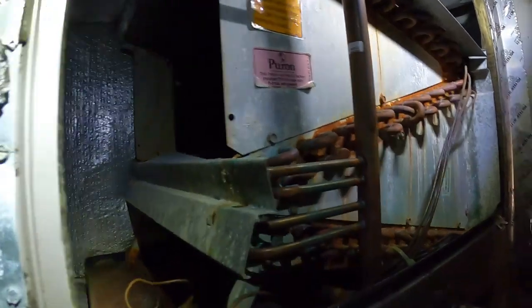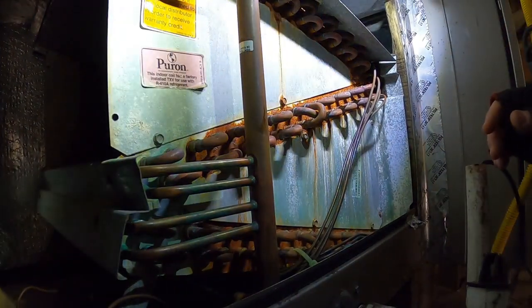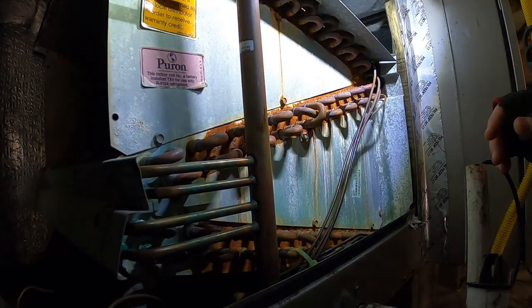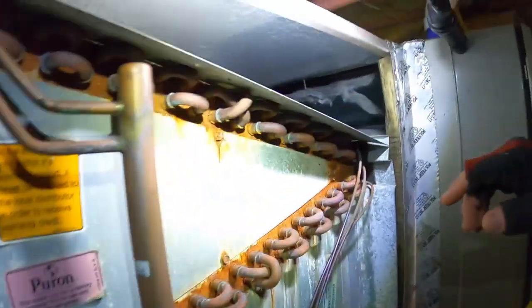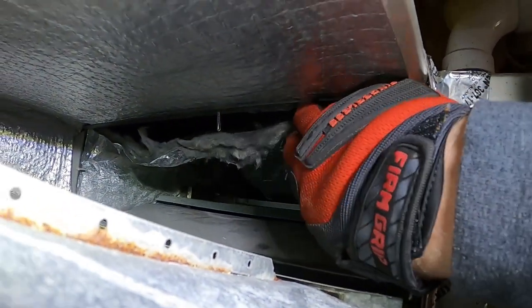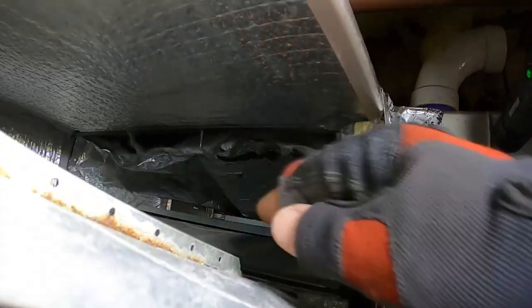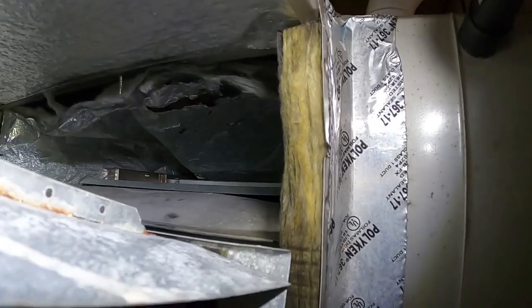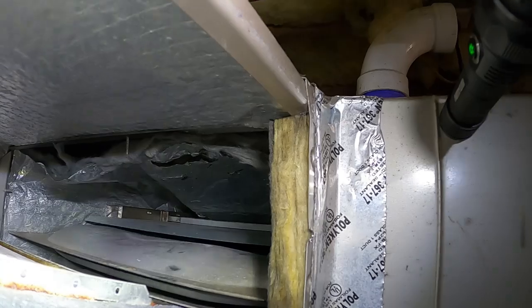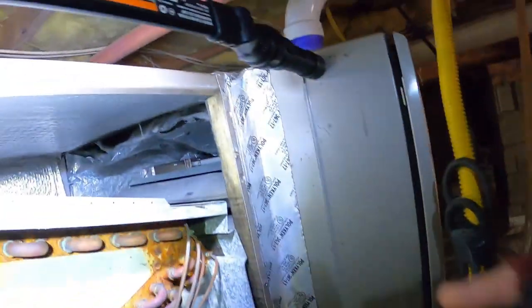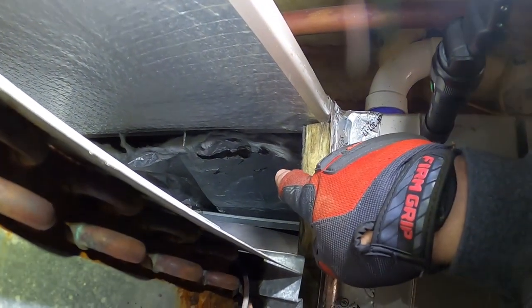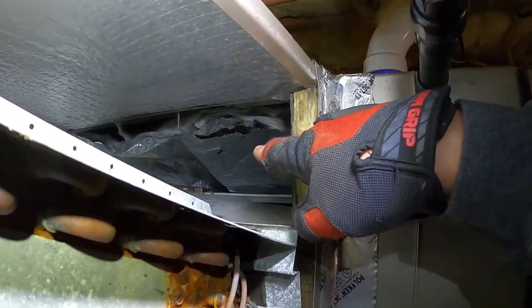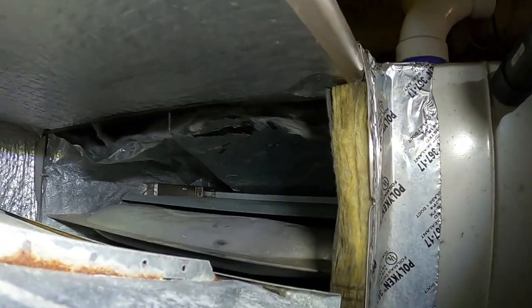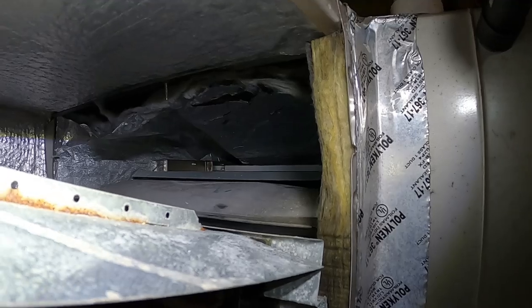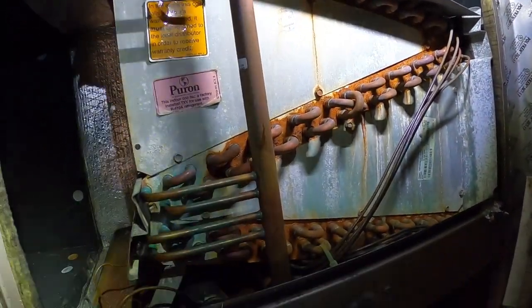We didn't do that the other day - should have. And it's 410A, so it won't be as expensive as an R22 coil, but it's not going to be cheap. And then we've got the insulation liner back here falling out of this furnace. I'm going to have to get some tape or something to see if I can get that up temporarily. We're coming out of the heating season, but if she's going to replace this thing, there's no way to get back in there - it's inside the furnace, and it's got a secondary heat exchanger on it because it's a 90% furnace. So there's no way to get in from the other side by pulling the blower out to tack that up out of the way. The air is catching it back there and peeling it down, and eventually it's going to be laying on top of that heat exchanger, and that's not going to be good. So I'm going to try to tack it up a little bit best I can, but we're going to get her a price on this coil, and then she's probably going to end up going with the system replacement.